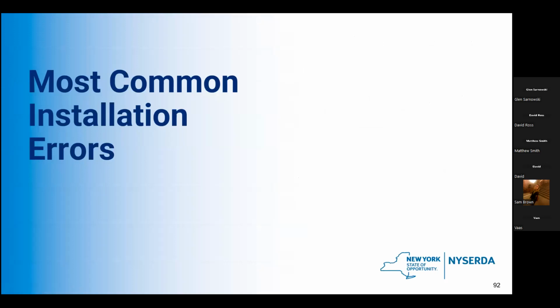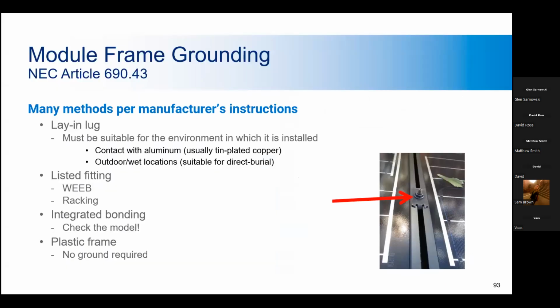All right, so now we'll go through some of the most common installation errors that we've seen over the 4,000 inspections that have been done by NYSERDA. We talked about this several times already, but it's important to ensure the system grounding is done properly. It could be the clamps are loose, or the integrated bonding system is not compatible with the panel racking system, or they're just not using the bonding system correctly. If the system is not grounded, it can cause serious injury or death. So it's very important to get right.